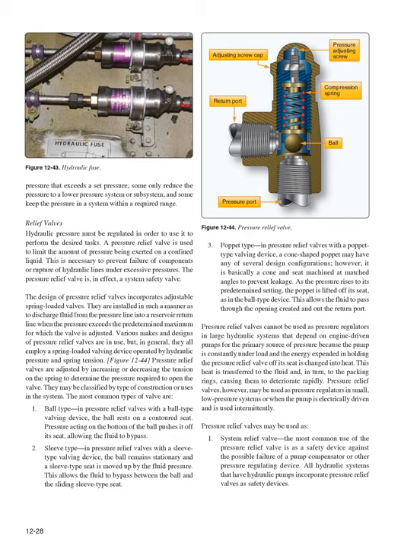Pressure relief valves cannot be used as pressure regulators in large hydraulic systems that depend on engine-driven pumps for the primary source of pressure because the pump is constantly under load and the energy expended in holding the pressure relief valve off its seat is changed into heat. This heat is transferred to the fluid and, in turn, to the packing rings, causing them to deteriorate rapidly. Pressure relief valves, however, may be used as pressure regulators in small, low-pressure systems or when the pump is electrically driven and is used intermittently.